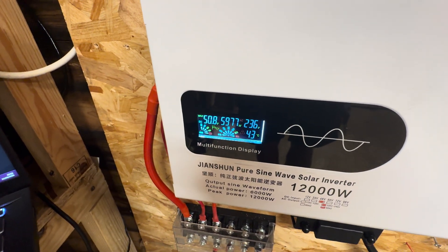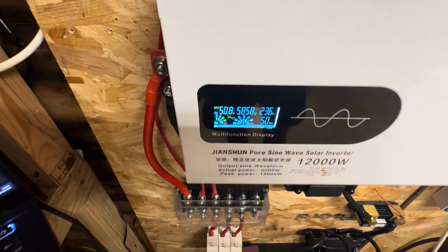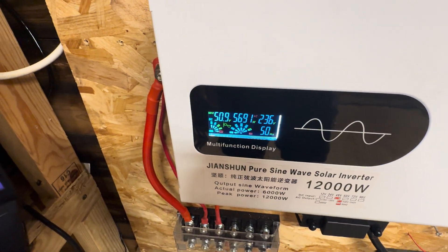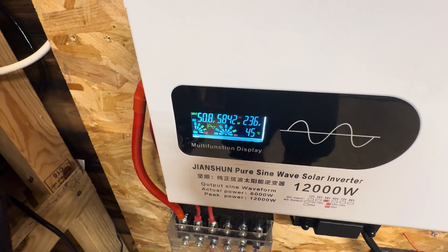The question is how long can it sustain it for? It's at 5.9 on one display and 5.7 on the other. Bit of an annoying beep, although the fans aren't really on at all, which is very impressive. Voltage seems to be at around 236. It's showing 5.8 kilowatts here and 5.6 kilowatts there. The beeping has momentarily gone — I'm not sure if the power turned off for a split second, but I don't see any dimming.